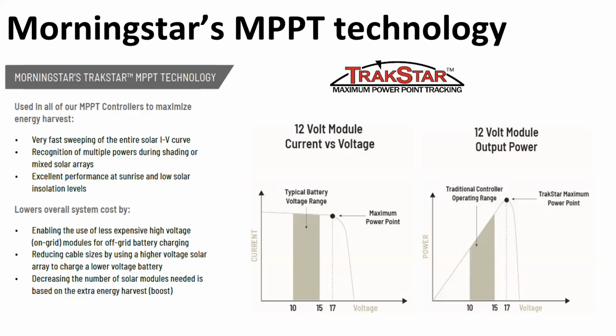However, PWM controllers typically can only operate based on whatever the battery voltage range is. So if it's a 12 volt battery, you're going to get swings from 10 to 15 volts depending on state of charge. You're only able to harvest this amount of power under the curve, and you're losing a lot of additional power that could be harvested if you were able to step up the voltage, step down the voltage, and increase the current. That's really what the MPPT controllers do.